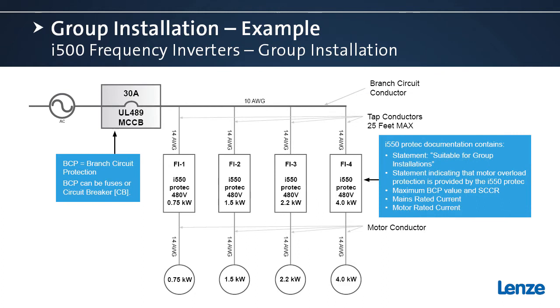So here's a little bit more detail about that example and the methodology for calculation. You can see here we have our 30 amp UL489 listed molded case circuit breaker, our branch circuit conductors 10 gauge, our tap conductors 14 gauge, our motor conductors also 14 gauge. This is all based on the calculations we did a moment ago. The one distinction I want to make here is the length limitation of the tap conductors. In this example, they're limited to 25 feet.